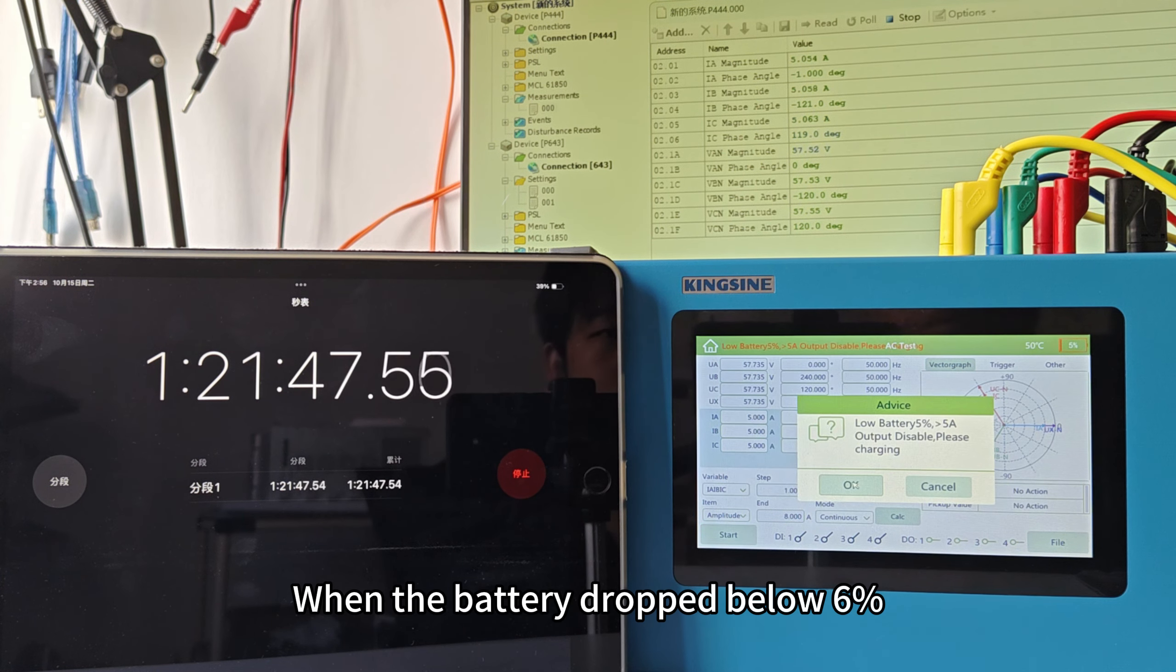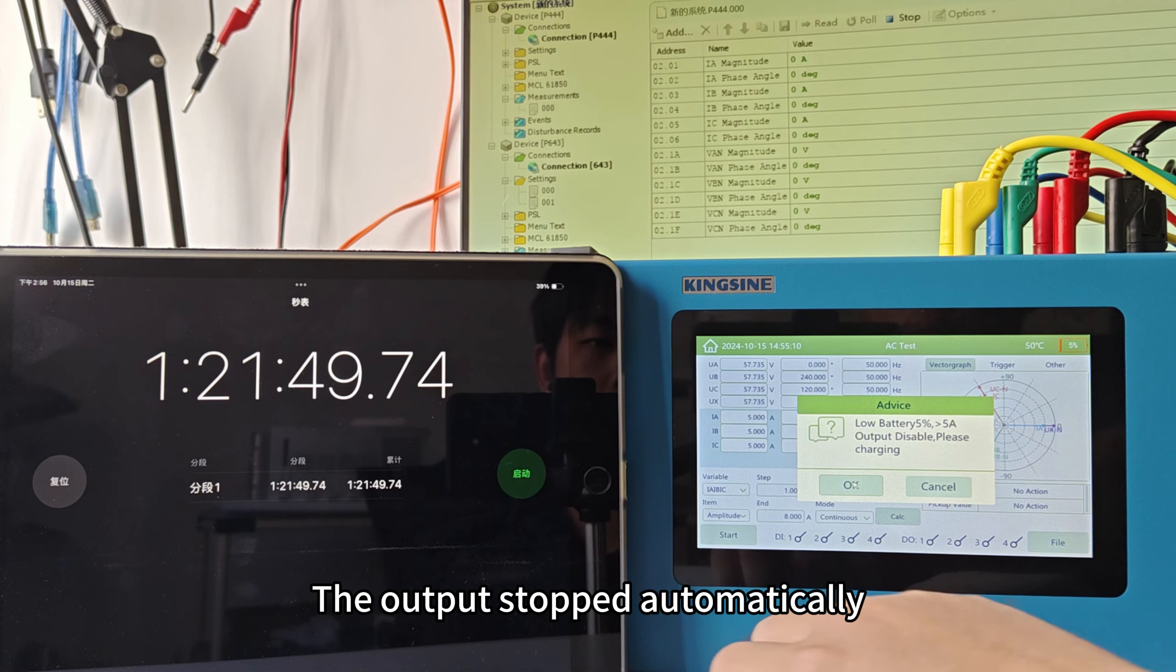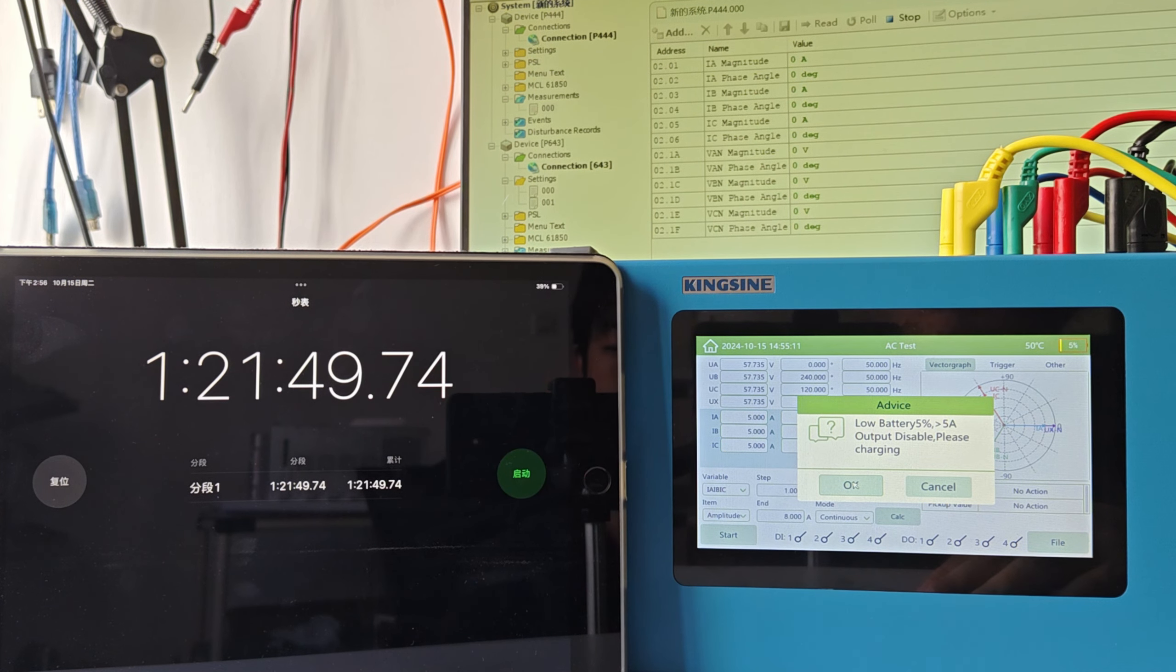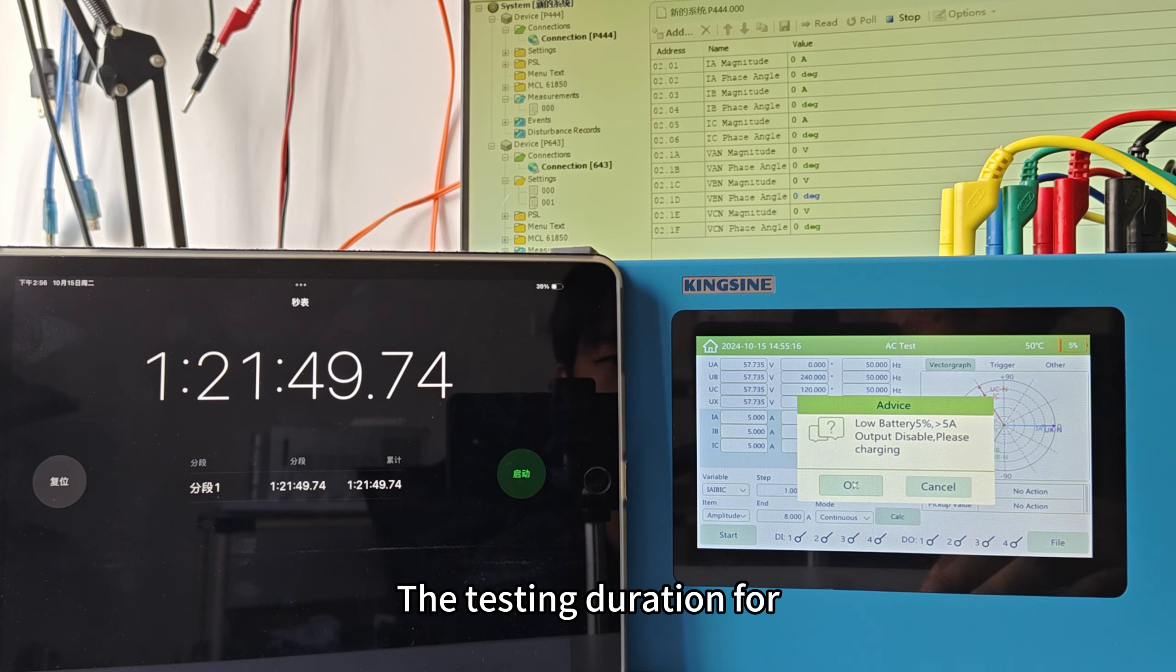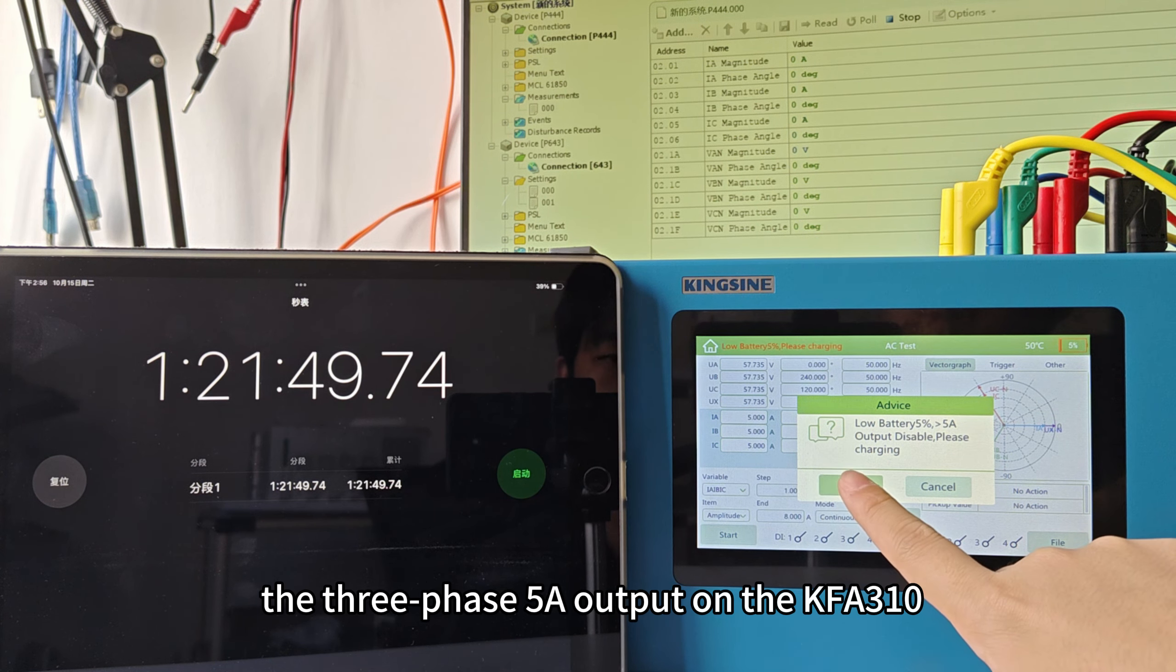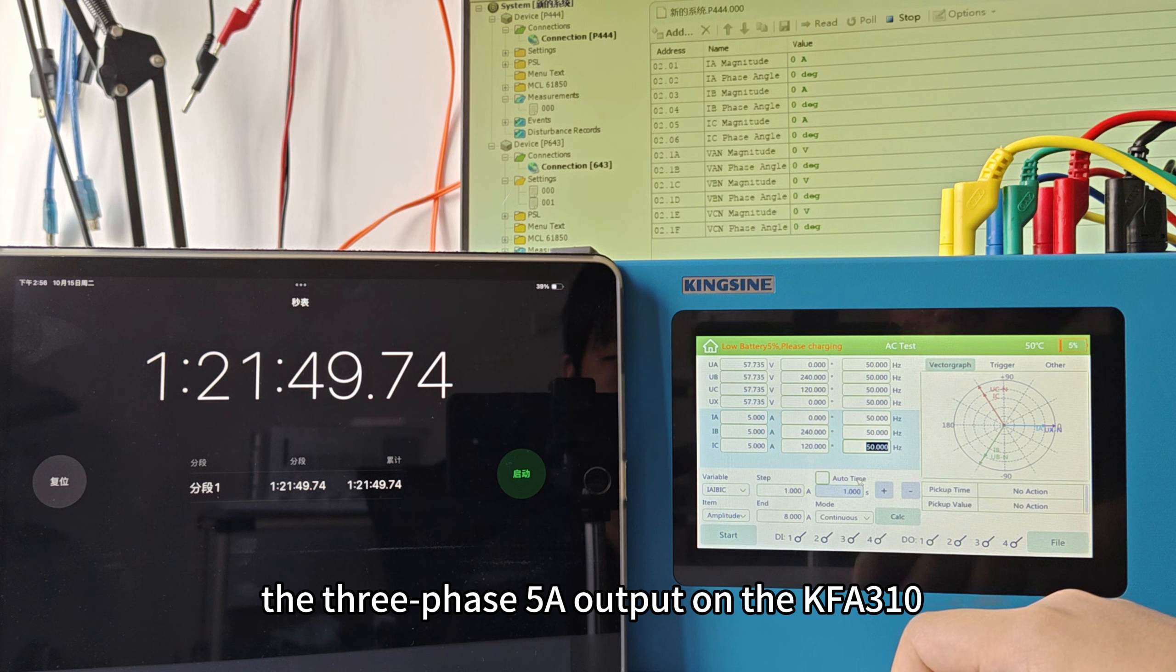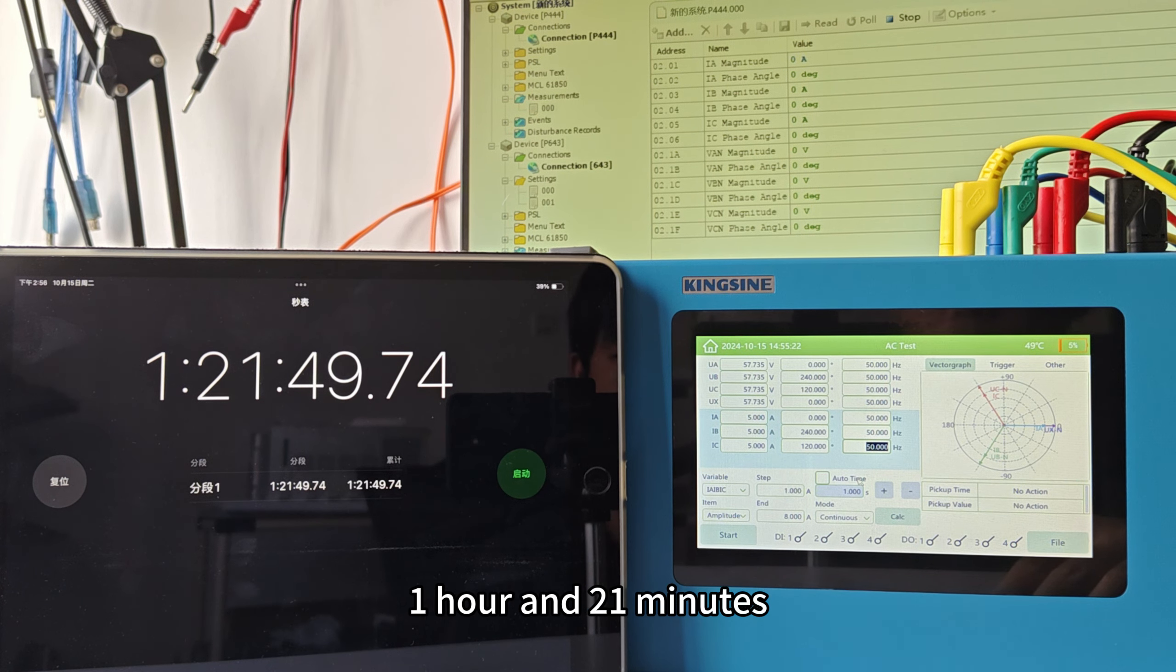When the battery dropped below 6%, the output stopped automatically. The testing duration for the three-phase 5 amps output on the KFA310 when fully battery-powered was approximately 1 hour and 21 minutes.